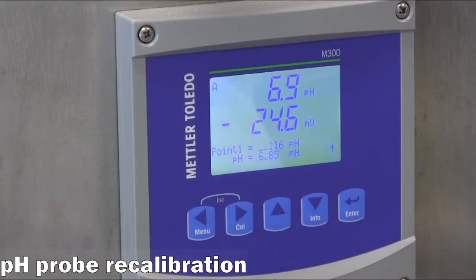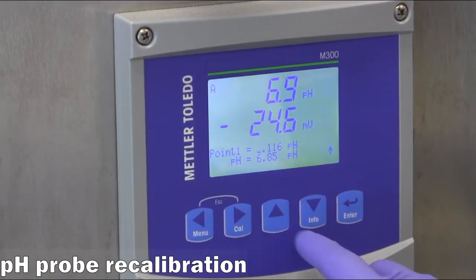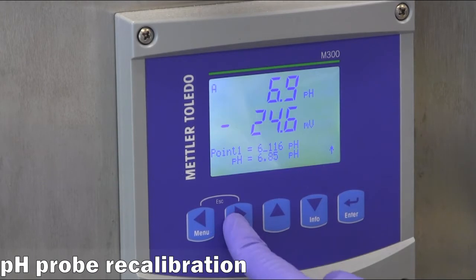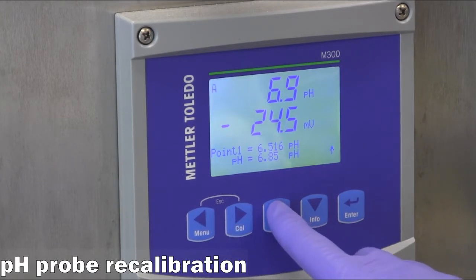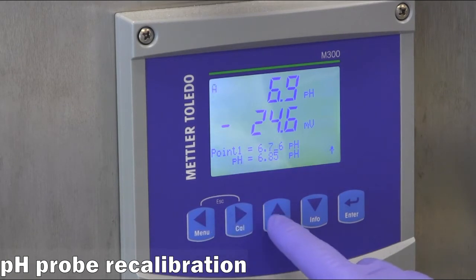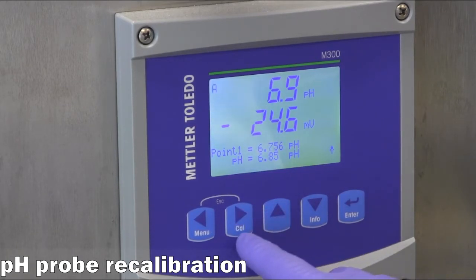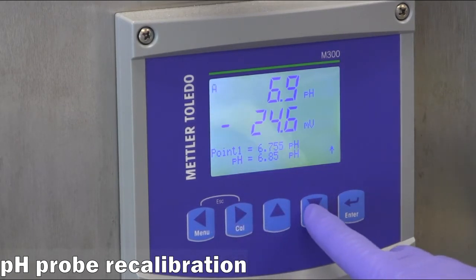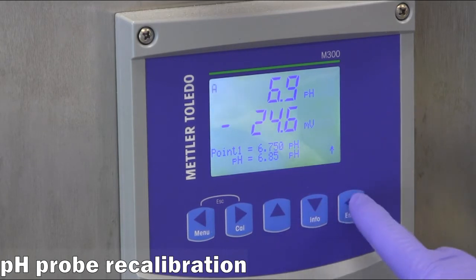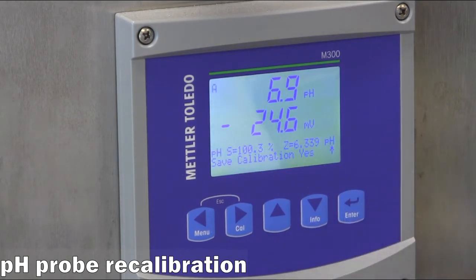Run through the same pH probe calibration procedure outlined before, but select Process as the type of calibration and enter the offline pH value. Record and save the new calibration. With confidence in the pH signal, the pH is adjusted to the final target.